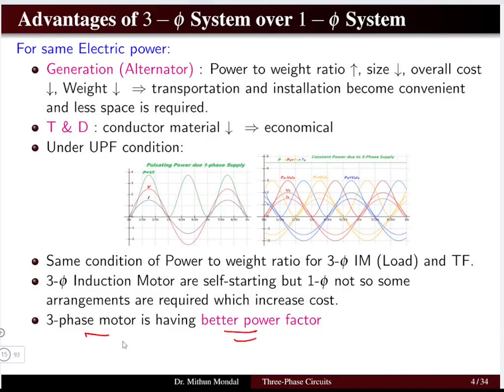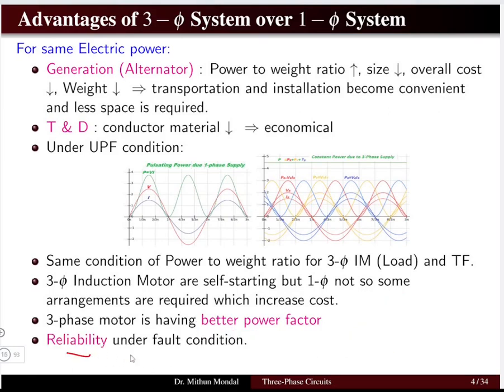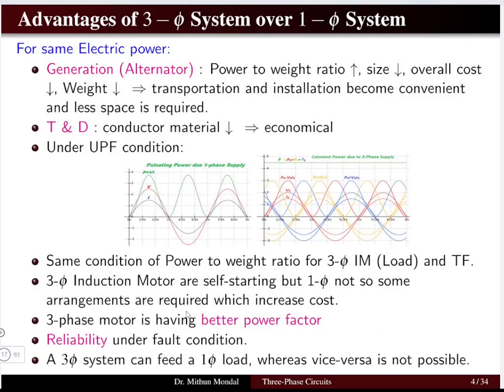Three-phase motors also have a better power factor compared to single-phase, meaning the value of cos phi is higher, which reduces reactive power and provides better real power consumption. Reliability is also better under fault conditions — if one phase fails in a three-phase system, the other two phases are still available for power transmission.